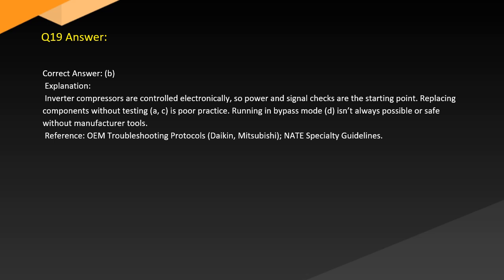Answer. Correct answer: B. Explanation. Inverter compressors are controlled electronically, so power and signal checks are the starting point. Replacing components without testing (A, C) is poor practice. Running in bypass mode (D) isn't always possible or safe without manufacturer tools. Reference: OEM troubleshooting protocols, Daikin, Mitsubishi, industry specialty guidelines.